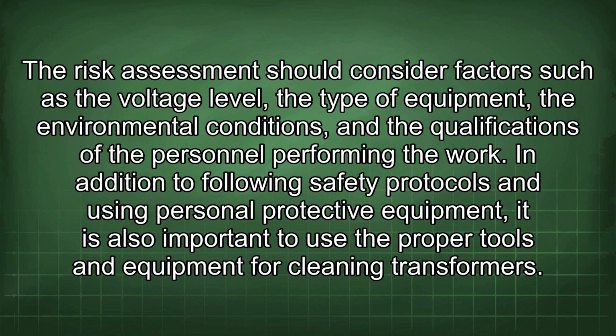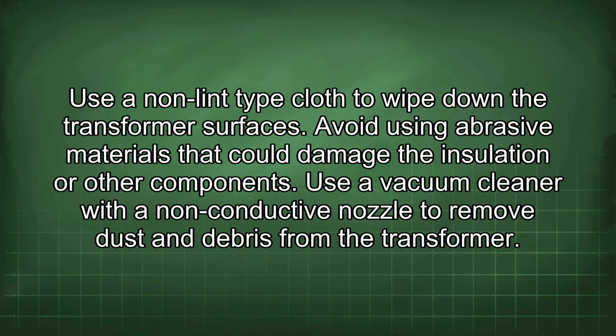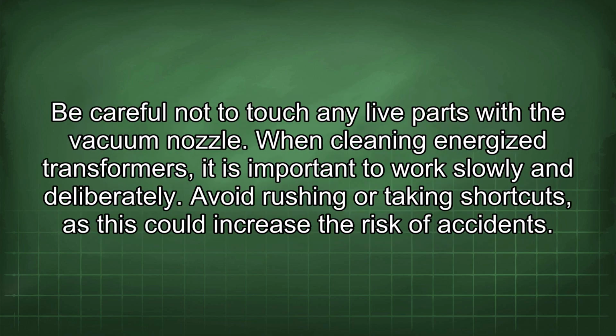In addition to following safety protocols and using personal protective equipment, it is also important to use the proper tools and equipment for cleaning transformers. Use a non-lint type cloth to wipe down the transformer surfaces. Avoid using abrasive materials that could damage the insulation or other components. Use a vacuum cleaner with a non-conductive nozzle to remove dust and debris from the transformer. Be careful not to touch any live parts with the vacuum nozzle.